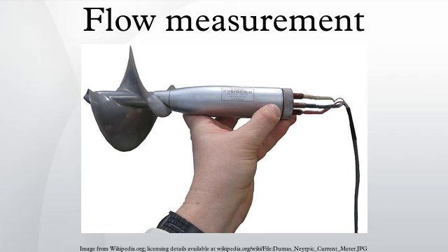Vortex flow meters, another method of flow measurement, involve placing a bluff body in the path of the fluid. As the fluid passes this bar, disturbances in the flow called vortices are created. The vortices trail behind the cylinder, alternatively from each side of the bluff body. This vortex trail is called the von Karman vortex street after von Karman's 1912 mathematical description of the phenomenon. The frequency at which these vortices alternate sides is essentially proportional to the flow rate of the fluid.